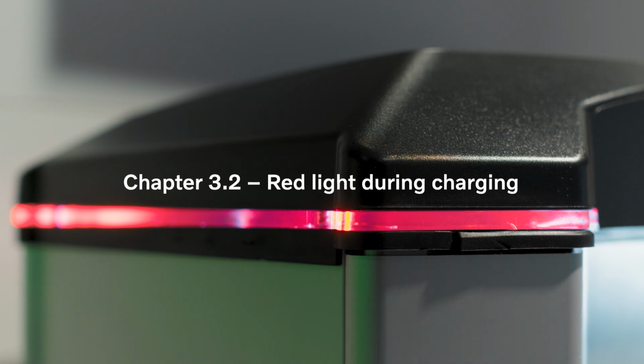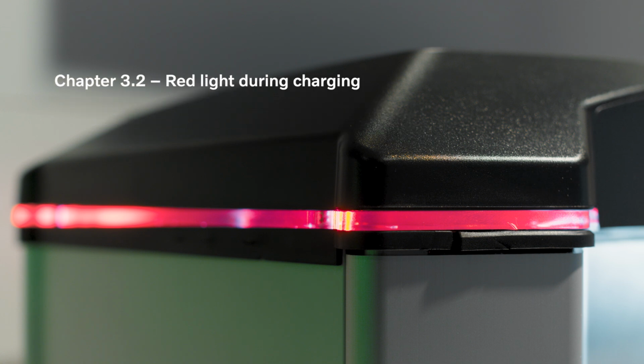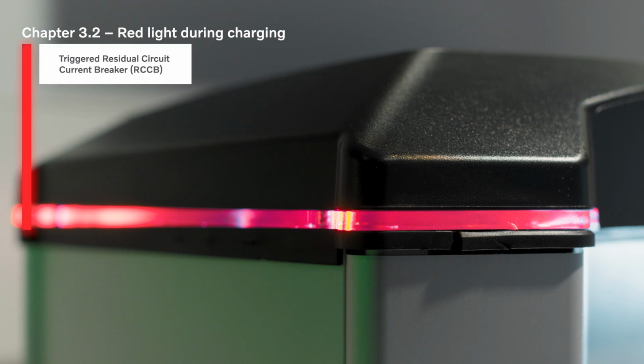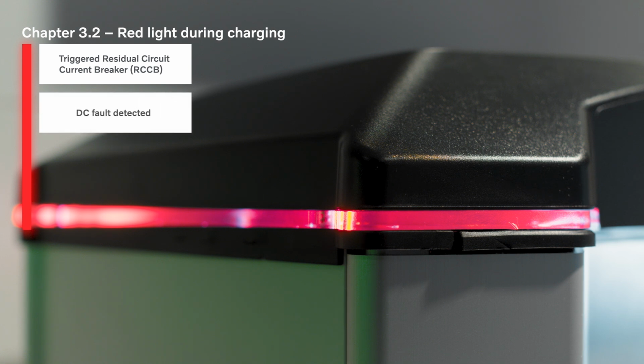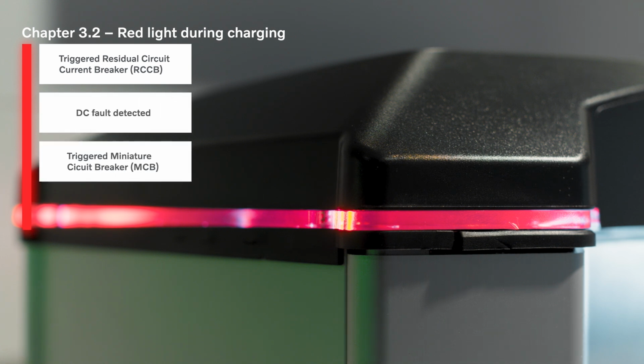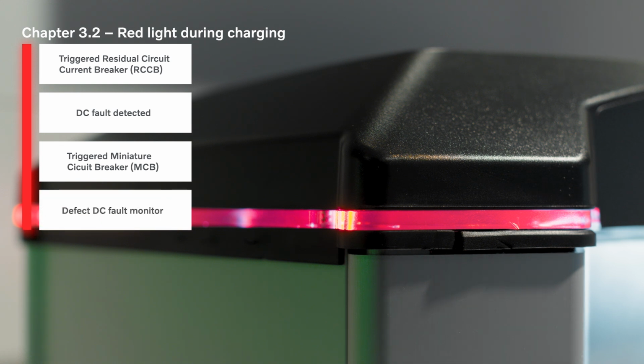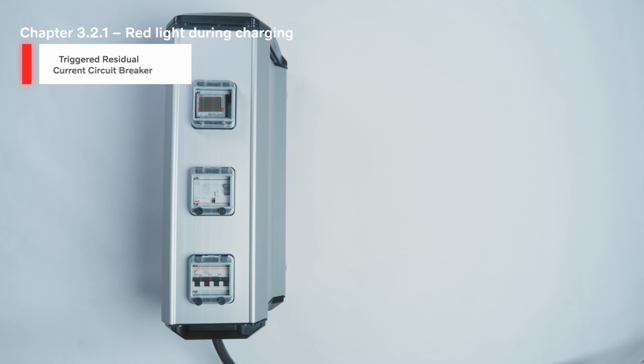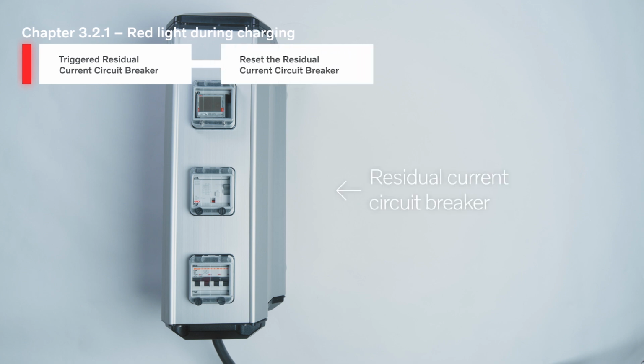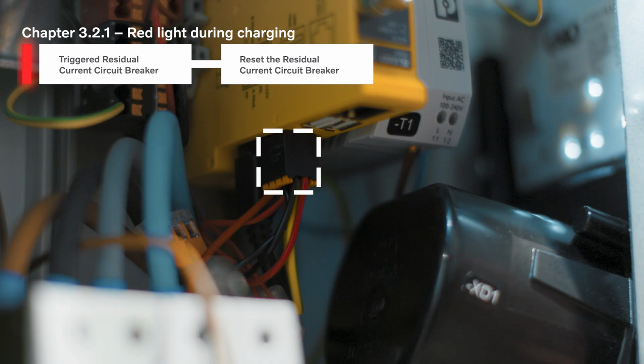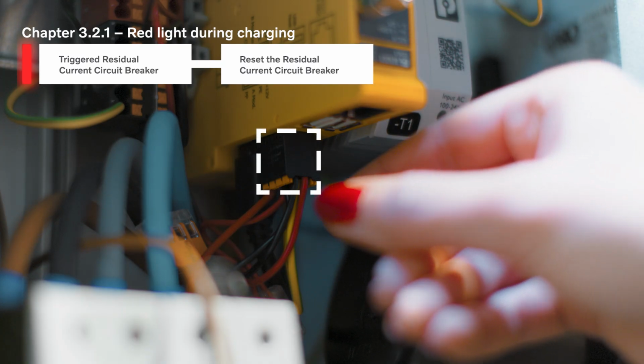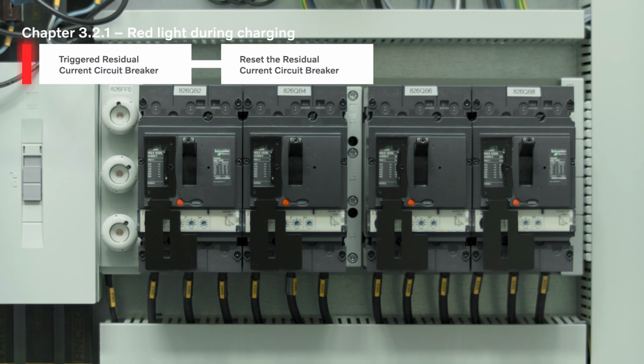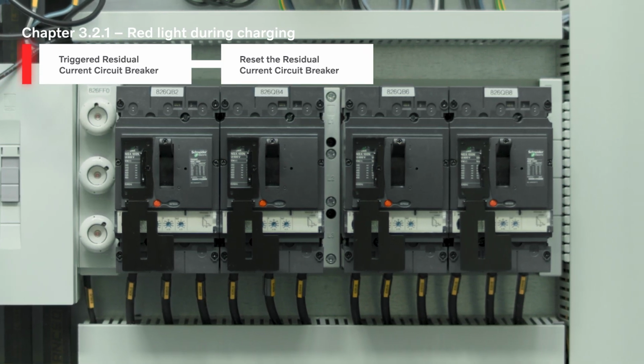If the red light appears during charging, this might be caused if the residual circuit current breaker, the RCCB, has been triggered, if a DC fault is detected, if the miniature circuit breaker, the MCB, is triggered, or if the DC fault monitor is defect. If the residual current circuit breaker has been triggered, please reset it on the side of the charging station. Verify that the 8-pole quick connection on the charge controller is properly connected, and make sure that the grounding and the phases in the building's electrical system are correct.